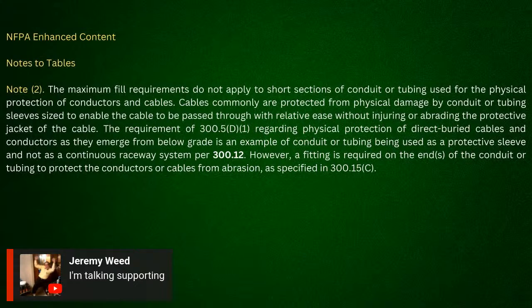Yeah, and we've been in this argument before. If you go into 358.30 A and B, my argument is it says in there that if you have an EMT within 3 foot of a stud, then you can use the stud as support. So that's totally fine. Now, let's just say you have one that's 30 inches. Nothing in the code says that a support's not required. It says must be securely fastened within 36 inches. Is 30 inches within 36 inches?